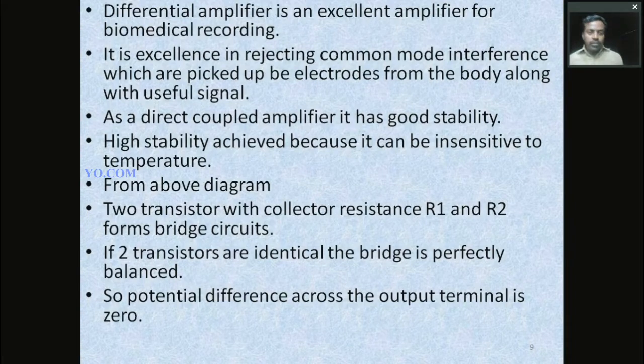Okay, right. So the differential amplifier is an excellent amplifier for biomedical recording. One of the most important amplifiers is the differential amplifier. It is the most excellent amplifier in biomedical recording because it produces very high gain, very low noise, and high CMRR. It is excellent in rejecting common mode interference, which takes place in an electrode from the body along with the useful signal. So the differential amplifier easily rejects the common mode interference coming from the electrodes.